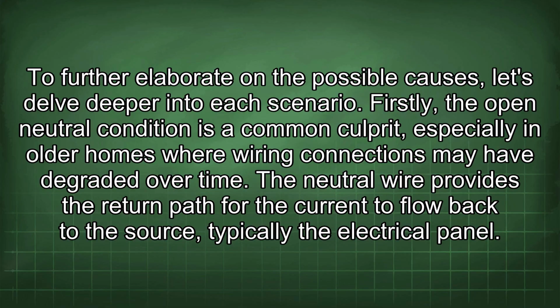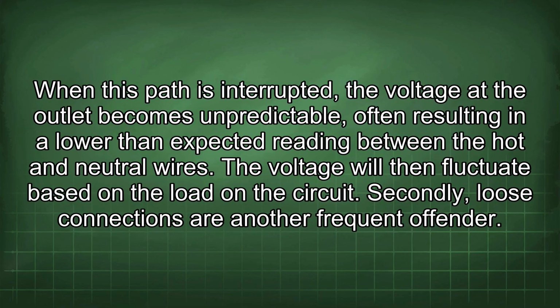Firstly, the open neutral condition is a common culprit, especially in older homes where wiring connections may have degraded over time. The neutral wire provides the return path for the current to flow back to the source, typically the electrical panel. When this path is interrupted, the voltage at the outlet becomes unpredictable, often resulting in a lower than expected reading between the hot and neutral wires. The voltage will then fluctuate based on the load in the circuit.